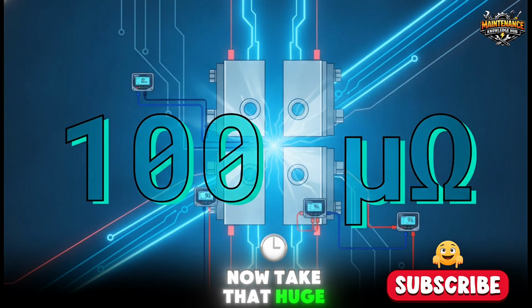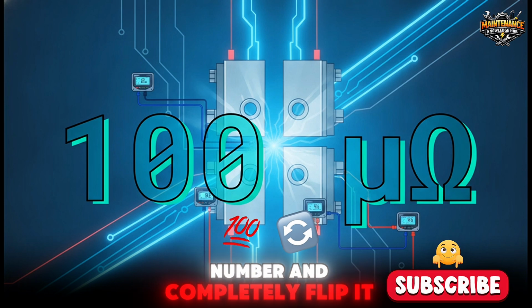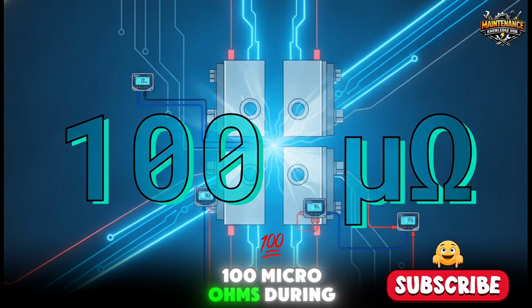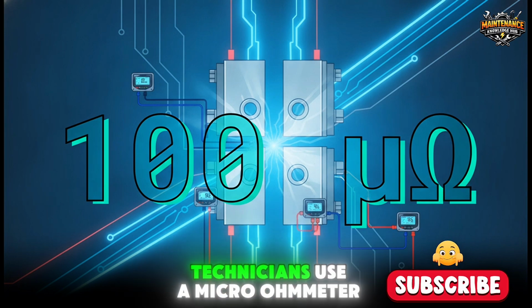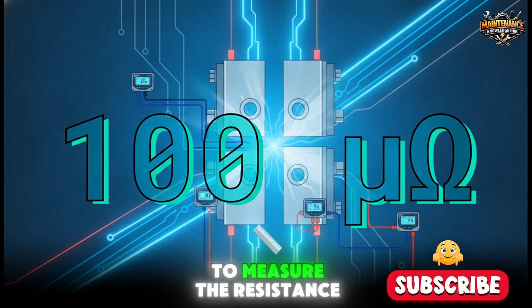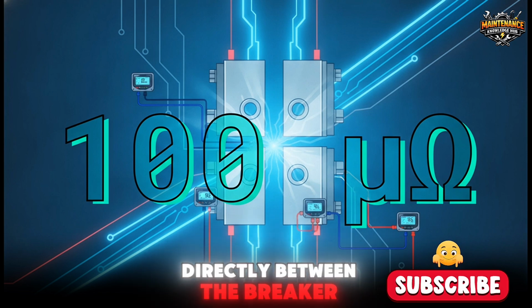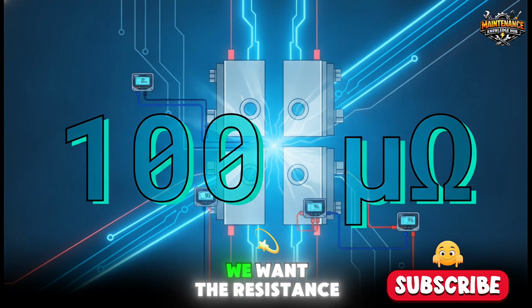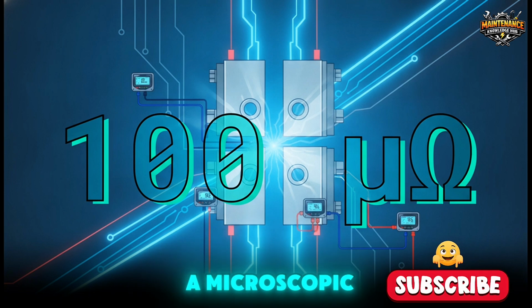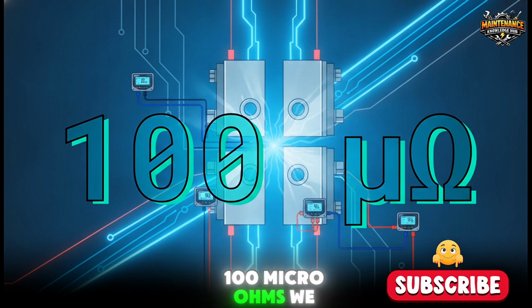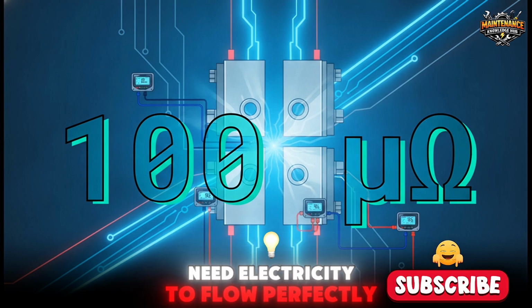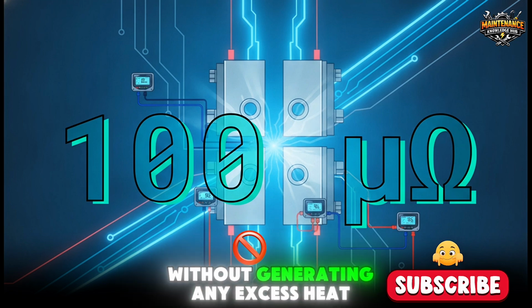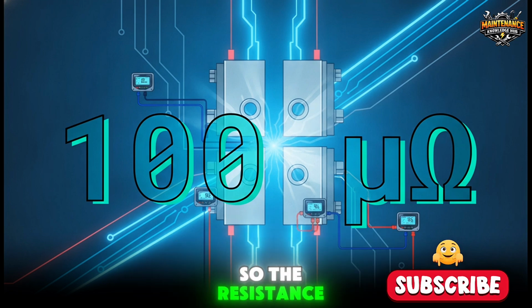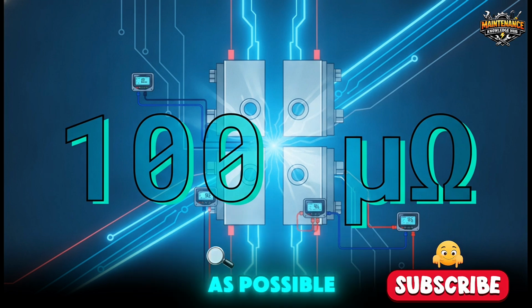Now, take that huge number and completely flip it, 100 microohms. During a contact resistance test, technicians use a microohmmeter to measure the resistance directly between the breaker contacts. And for this, we want the resistance to be less than a microscopic 100 microohms. We need electricity to flow perfectly through those contacts without generating any excess heat, so the resistance right there has to be as close to zero as possible.